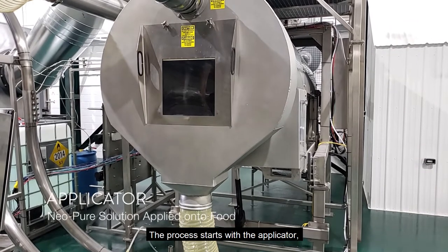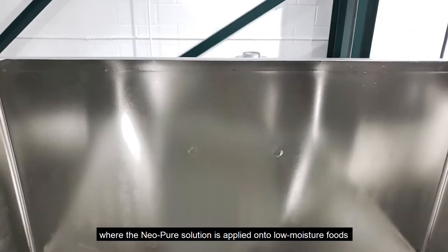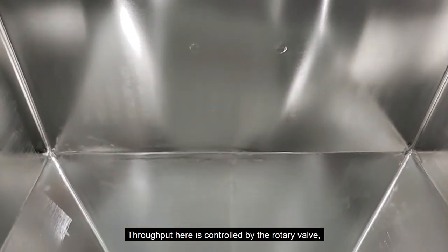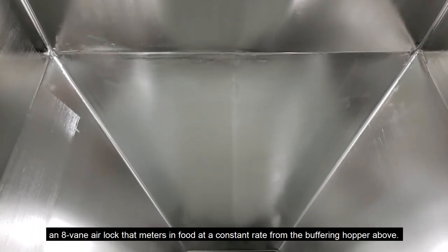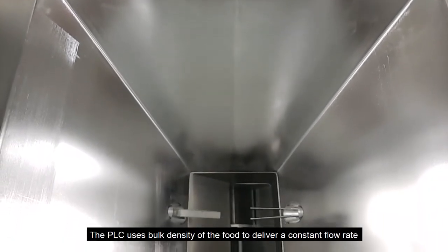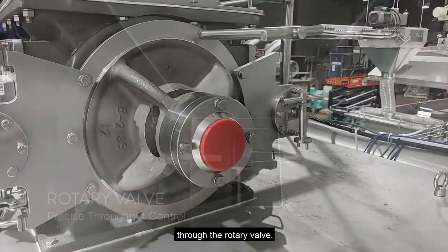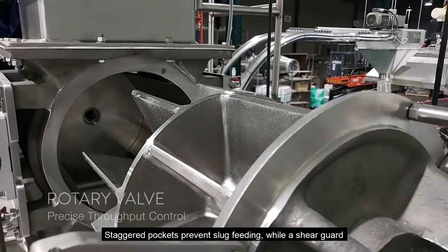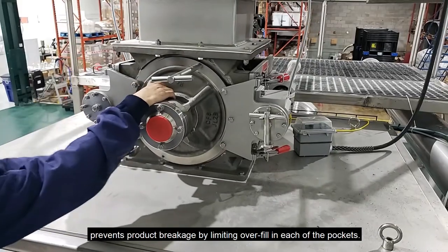The process starts with the applicator, where the Neopure solution is applied onto the low moisture foods. Throughput here is controlled by the rotary valve, an eight-vane air lock that meters in food at a constant rate from the buffering hopper above. The PLC uses bulk density of the food to deliver a constant flow rate through the rotary valve. Staggered pockets prevent slug feed, while a shear guard prevents product breakage by limiting overfill in each of the pockets.